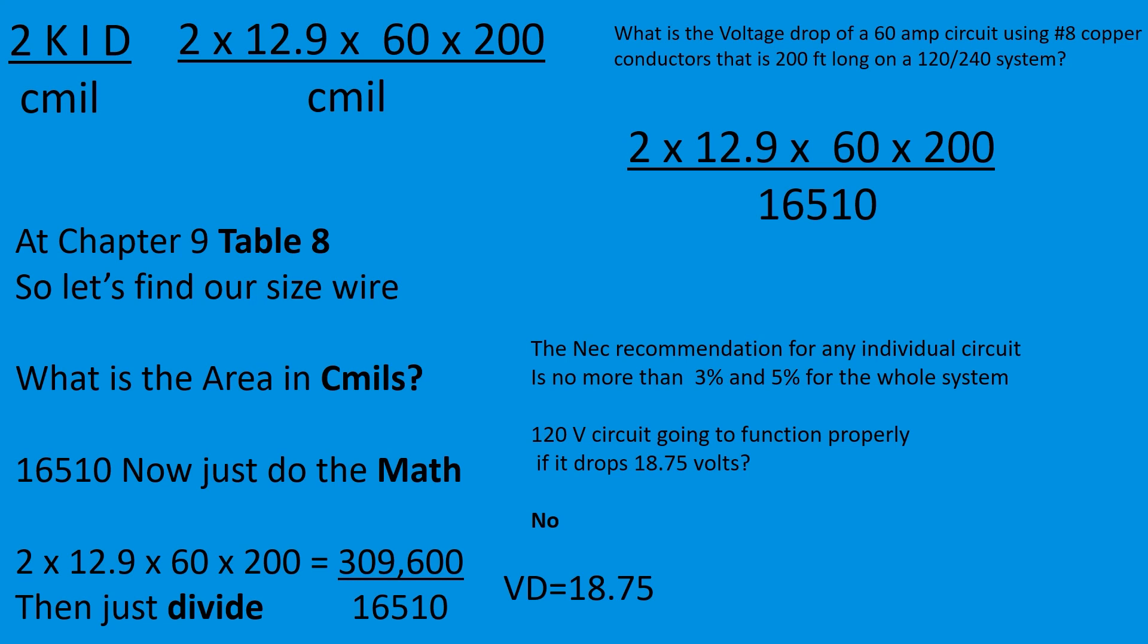Now the NEC recommendation, not code but recommendation, for any individual circuit is no more than 3% and 5% for the whole system. A 120 volt circuit, is it going to function properly if it drops 18.75 volts on the way? No. So this is not going to be an acceptable circuit. You're going to have to increase your wire significantly in order to compensate for this voltage drop in this circuit. So you could do the math and figure out what size wire you could use. And this is the fastest, easiest way to do voltage drop calculations.